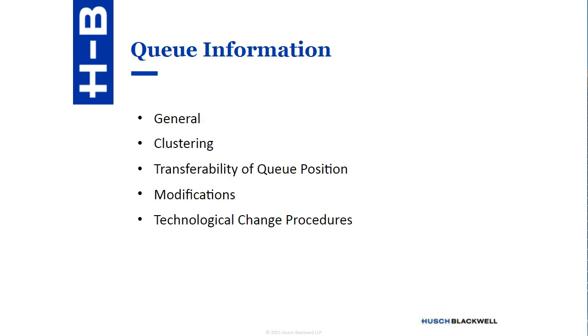As to queue information, generally the RTO or ISO assigns a queue position based on the date and time it receives a valid interconnection request. As discussed above, withdrawal results in a loss of queue position. Additionally, moving a POI, point of interconnection, results in a lower queue position if deemed to be a material modification. Queue position is used to determine the order of performing the interconnection studies and to determine cost responsibility for facilities necessary to accommodate the interconnection request.